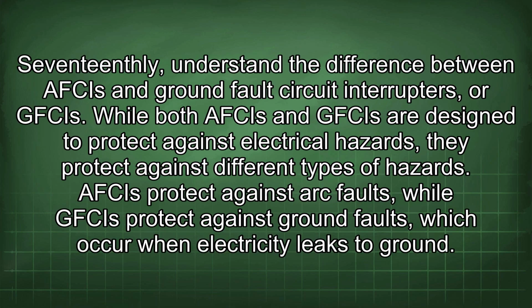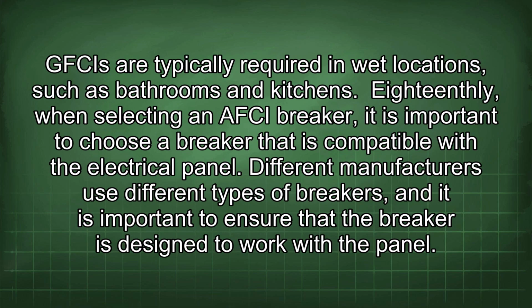17thly, understand the difference between AFCIs and ground fault circuit interrupters, or GFCIs. While both AFCIs and GFCIs are designed to protect against electrical hazards, they protect against different types of hazards. AFCIs protect against arc faults, while GFCIs protect against ground faults, which occur when electricity leaks to ground. GFCIs are typically required in wet locations, such as bathrooms and kitchens.